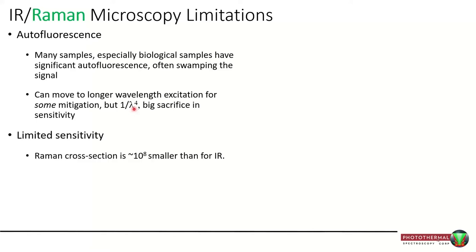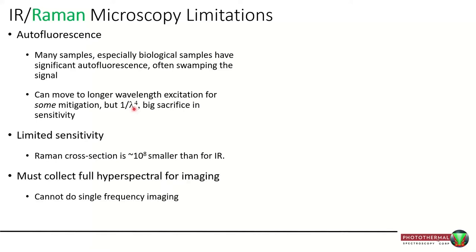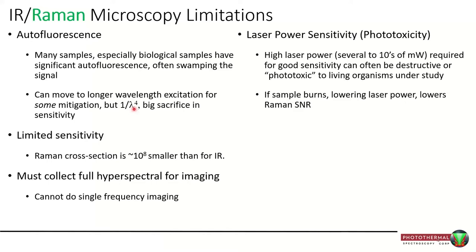Raman also has a fundamentally low Raman cross section — it's a limited sensitivity technique relative to infrared. You must collect in full hyperspectral mode if you want to do imaging; you can't do single-frequency imaging. For live biological work, phototoxicity can be a major issue: the more laser power you put in, the better the sensitivity, but at 10 milliwatts or more, live organisms aren't happy. So you have to operate at much lower power, which drops sensitivity and extends measurement time.